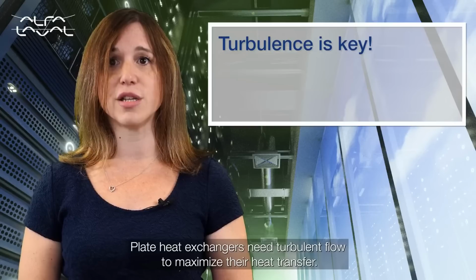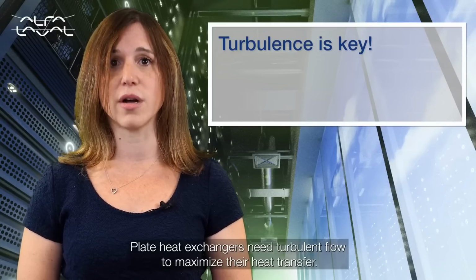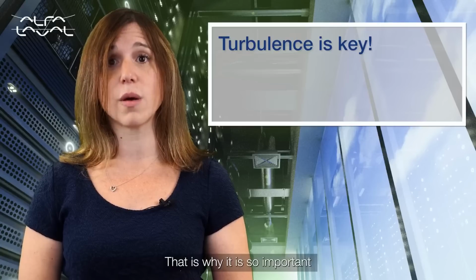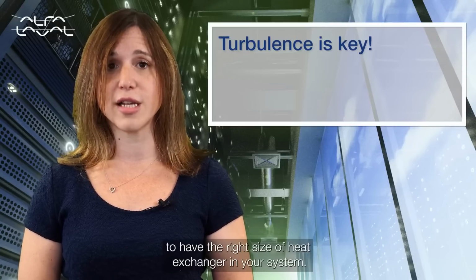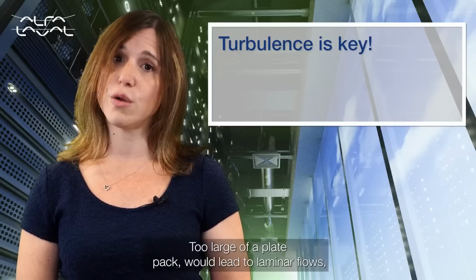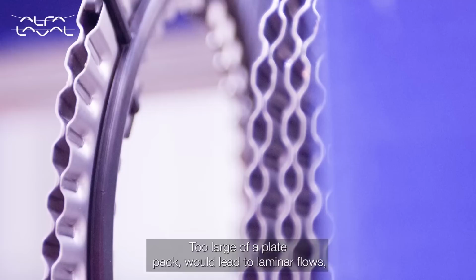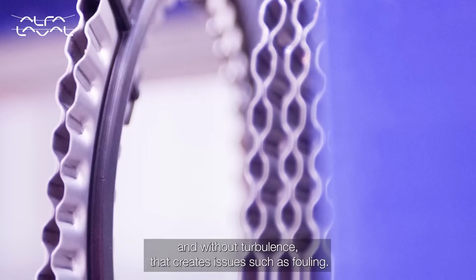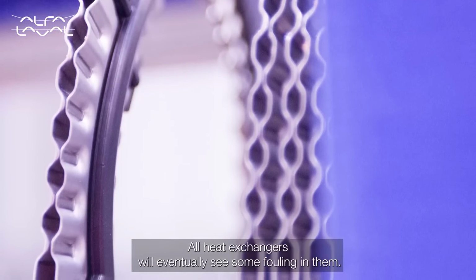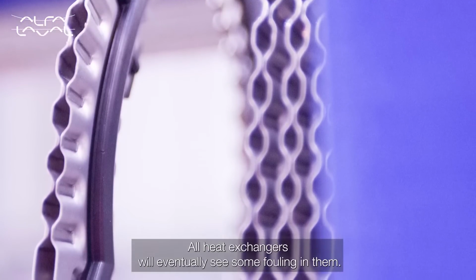Plate heat exchangers need turbulent flow to maximise their heat transfer. That is why it is so important to have the right size of heat exchanger in your system. Too large a plate pack will lead to laminar flows, and without turbulence, that creates issues such as fouling. All heat exchangers will eventually see some fouling in them.